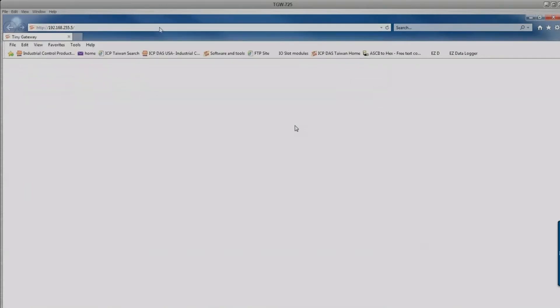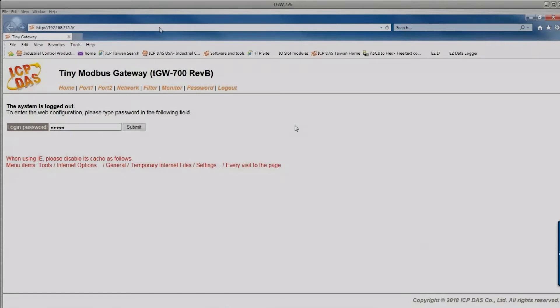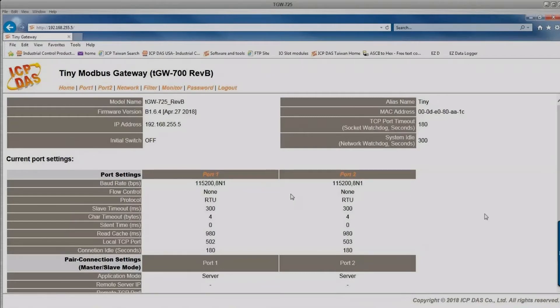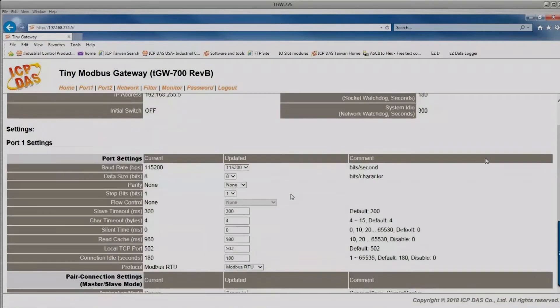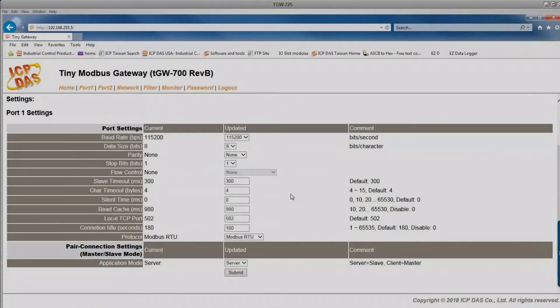The IP address in this example is 192.168.255.5. Enter it in the browser, type the admin password 'admin', and you reach the module overview page. This module has two COM ports — port 1 and port 2. Set the baud rate and parity to match your slave devices. Port 1 corresponds to TCP port 502, and port 2 to TCP port 503, allowing two independent RS-485 networks each with their own Modbus address space.